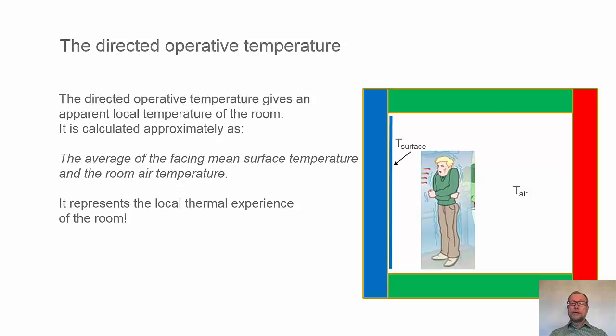But in the picture with the man we see that he might get a net exchange losing energy towards the cold window. We can also define a directed operative temperature. This is the average of the facing mean surface temperature and the room air temperature, so it represents a local thermal experience of the room.